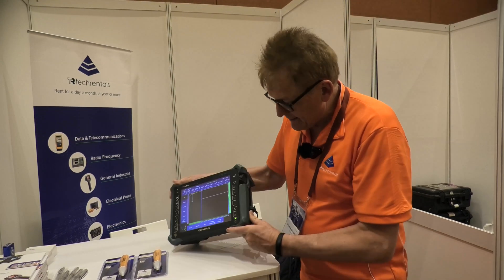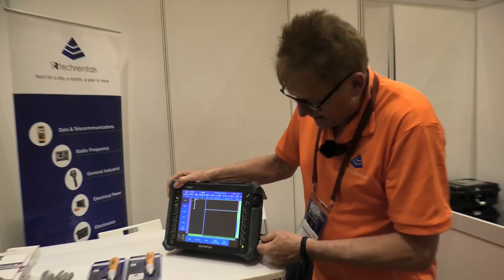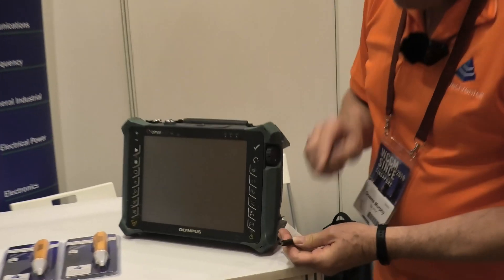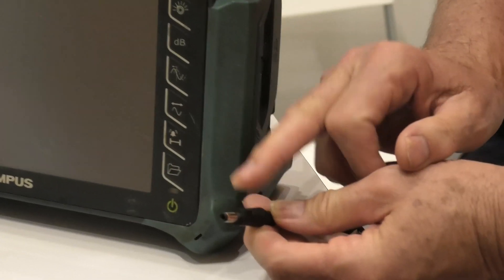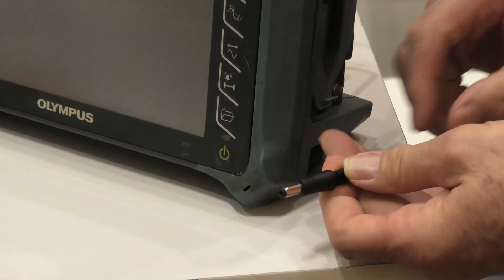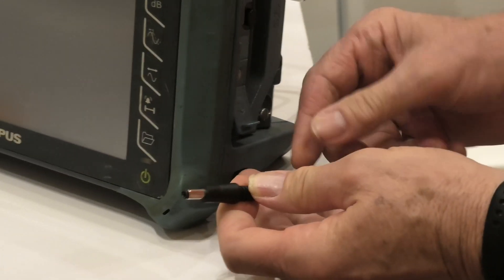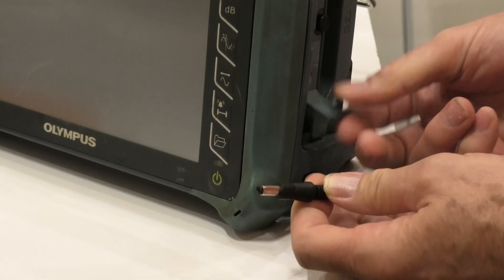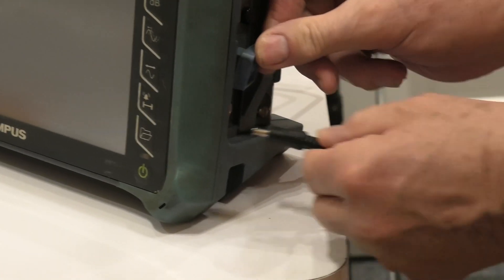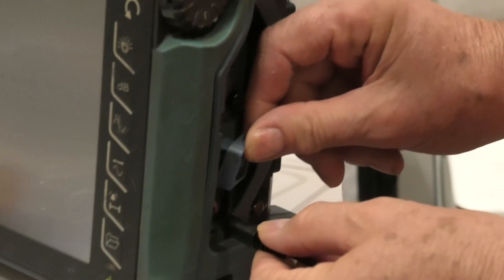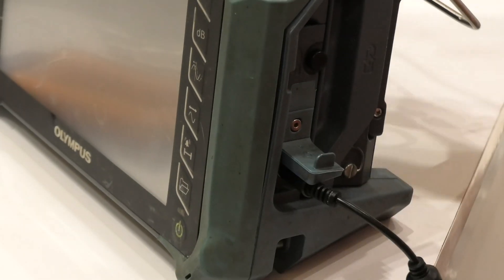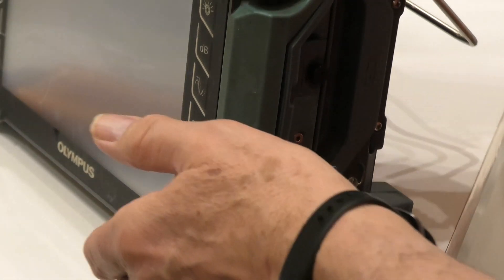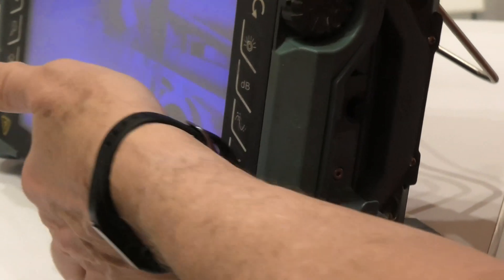One is the power connector on this thing. It's a standard connector, so make sure you use the power supply with the instrument, because if you plug the wrong voltage in, we can damage the instrument.